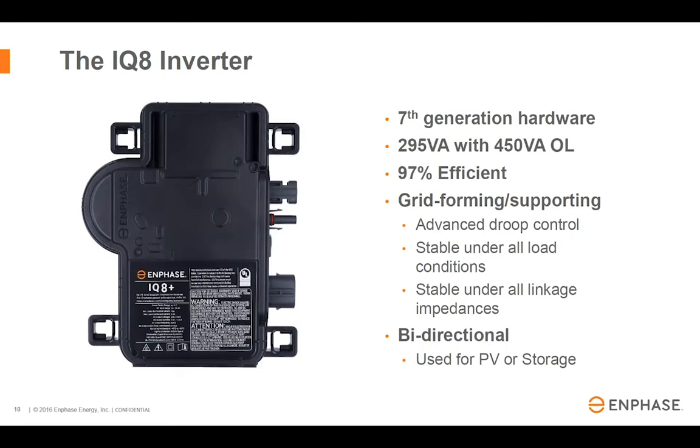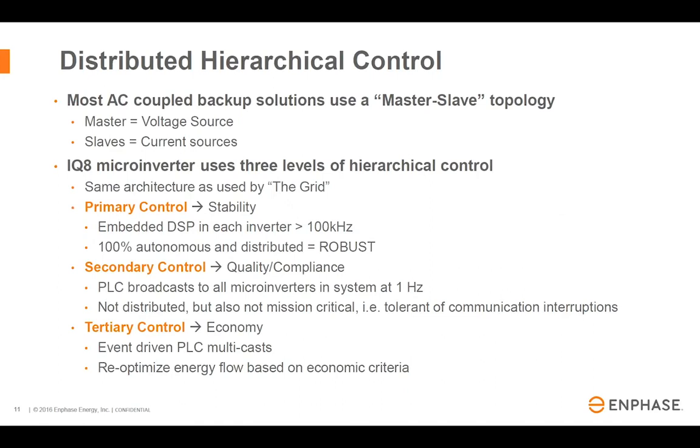So we actually use the same inverter for our solar and battery product, just different firmware. It uses a distributed hierarchical control system, basically identical to what was invented in the early 1900s by the utility. So we didn't invent this, right? We got a lot of our ideas for how to implement these controls from a book that was published in 1966.